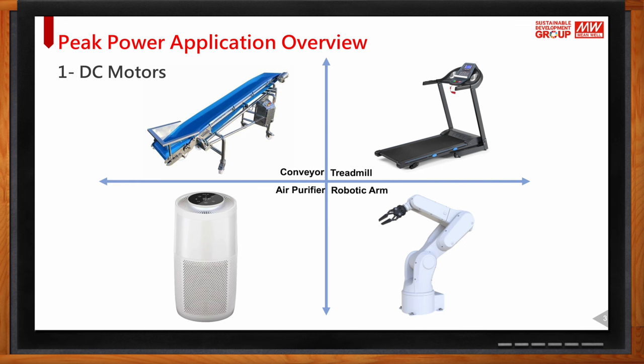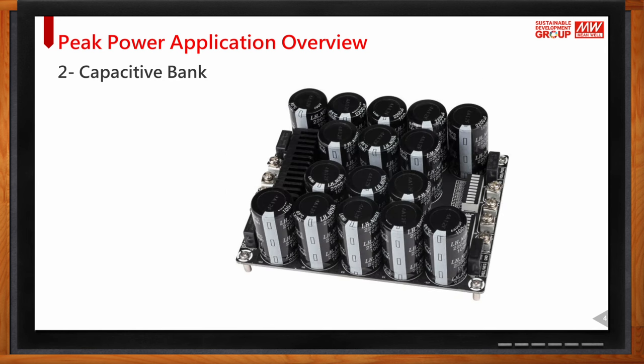That huge startup current forces the power supply into overload protection. Customers have two solutions: purchase a power supply with a higher power rating, or purchase a power supply with peak power capability. Capacitive banks at startup also require huge current, similar to motors, because the internal resistance of the capacitors is very low at startup — requiring huge current and power, which causes the power supply to trigger overload protection and shut down.